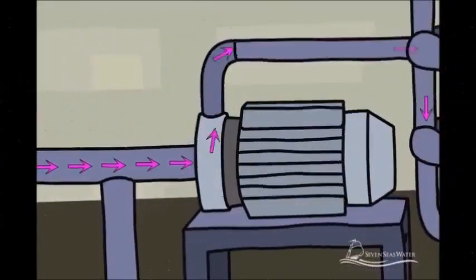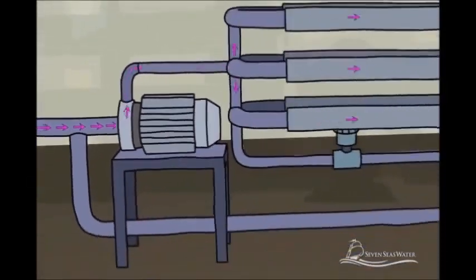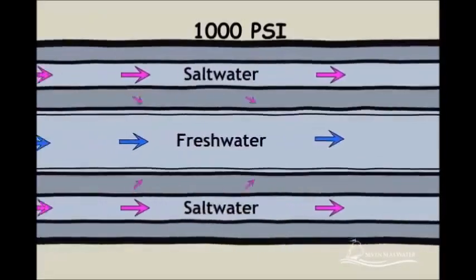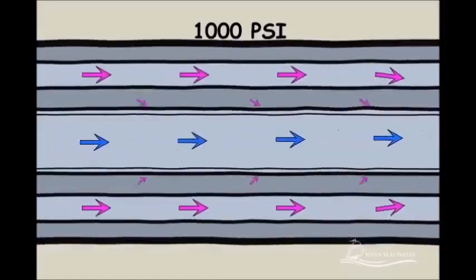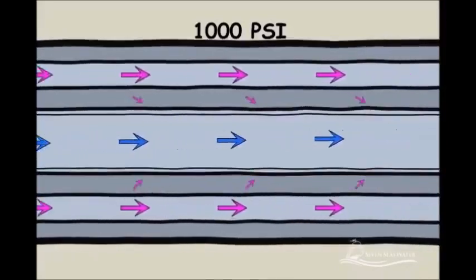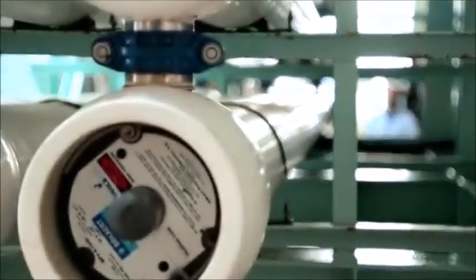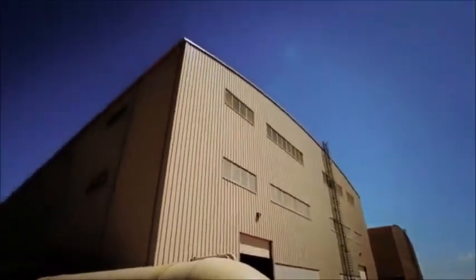High-pressure pumps increase the pressure of the seawater up to 1,000 psi. The pressure needs to be sufficiently high to overcome the naturally occurring osmotic pressure and force water from the salt water side, through the reverse osmosis membranes, to the freshwater side. In reverse osmosis, salt water is pumped through semi-permeable membranes to separate water from the dissolved salts.